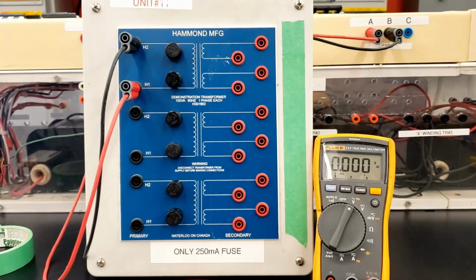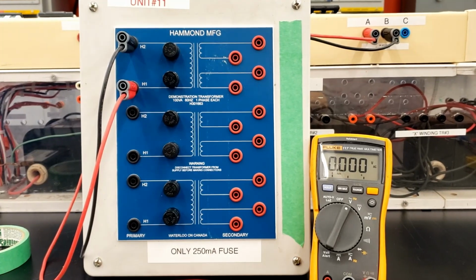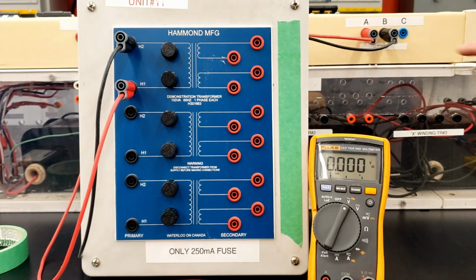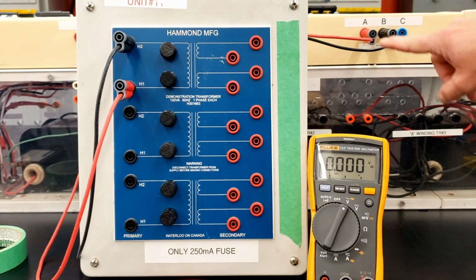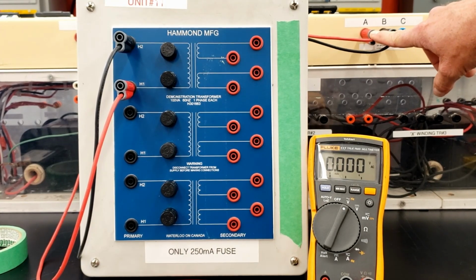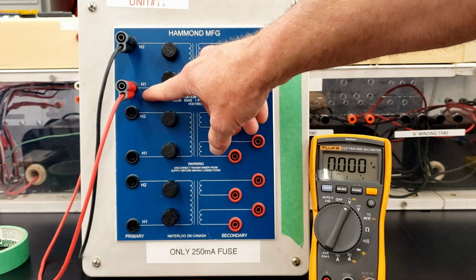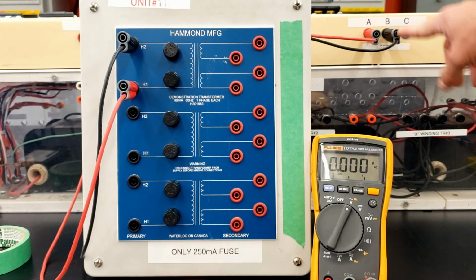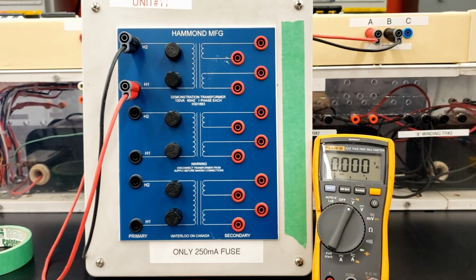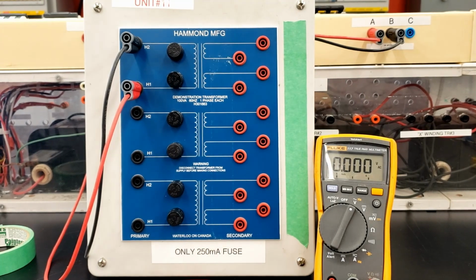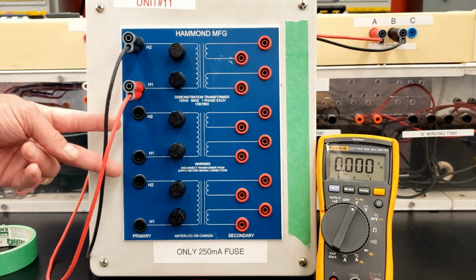You can see I put some painter's tape here so I can label my secondary windings. First we're going to put the feed: I have my 3 amp breaker here, bringing line 1 or the A phase to H1, and line 2 or the B phase to H2. As we do each transformer, keep this polarity the same for every one.